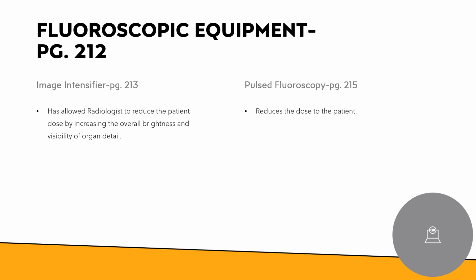The Bucky slot cover has to be 0.25 millimeters of lead, and the protective curtain that hangs down from the image intensifier has to be 0.25 millimeters of lead. The fluoro tower is required to have equivalent shielding of 2 millimeters of lead, and that is considered a primary barrier. You can also look at page 811 in your imaging procedures book.